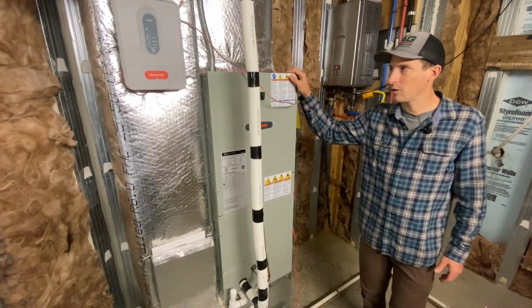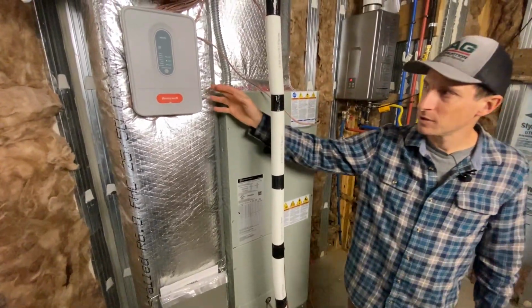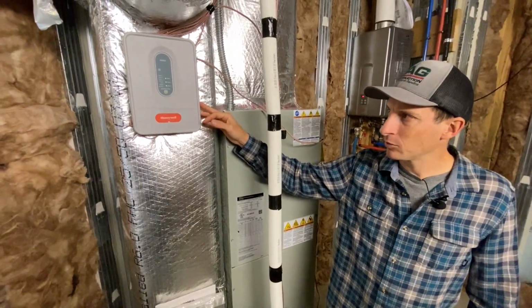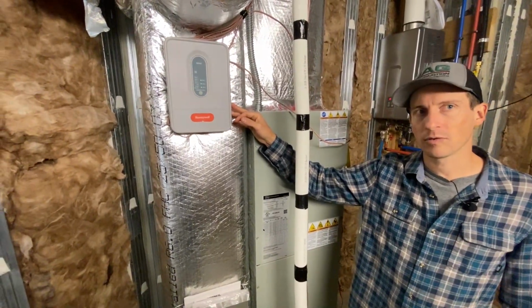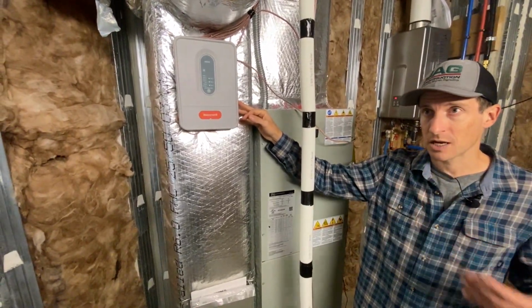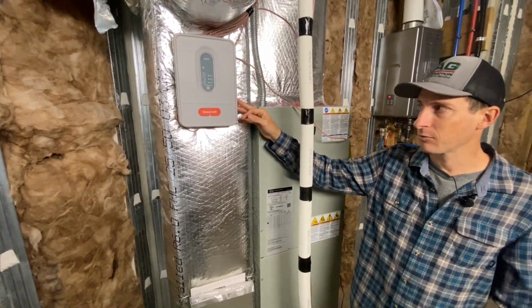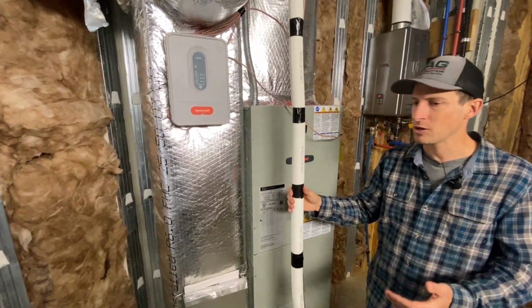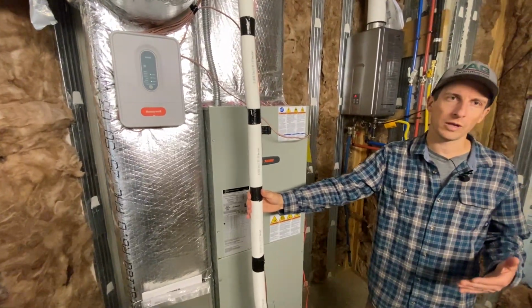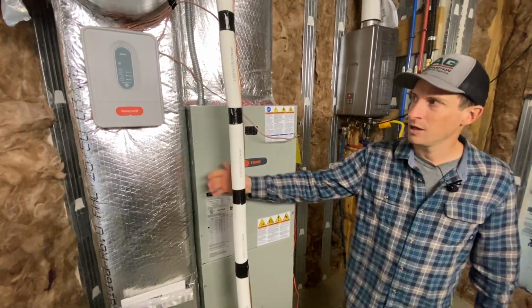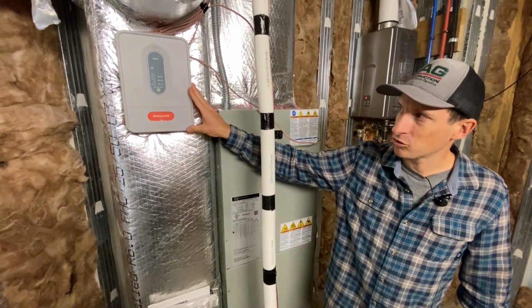Another thing I wanted to point out was the zone control system. So every one of our homes is going to have multiple zones. If a house has 2 floors, it's going to have 2 zones. If it has 3 floors, it's going to have 3 zones. That means each zone has a separate thermostat to control the heating and cooling for that area of the home. This is the brain that controls that.